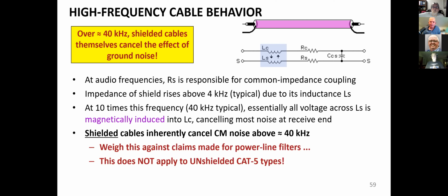Now the logical question is, how do I know if I have a common mode rejection problem in a Cat5 interface? Well, you might not if it's a digital signal — it'll just work, and then all of a sudden it won't. Or somebody will flip a light switch and you'll get a big glitch or a dropout. The common mode voltage ranges on digital interfaces are pretty small — most of them are under a volt. If you move the pair with respect to ground by a volt or two, the receiver is going to basically stop working.